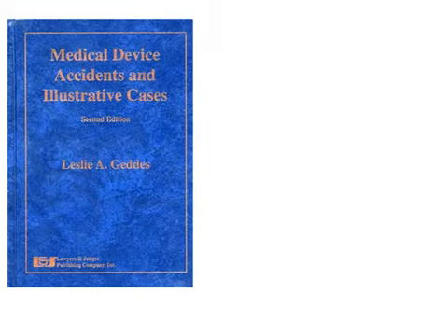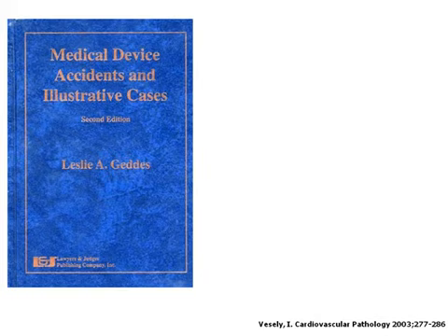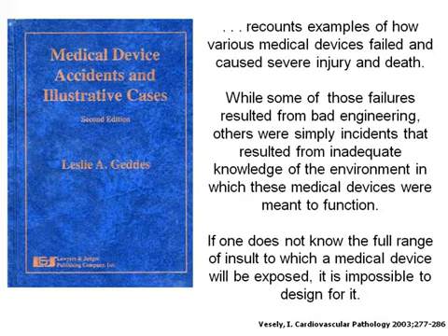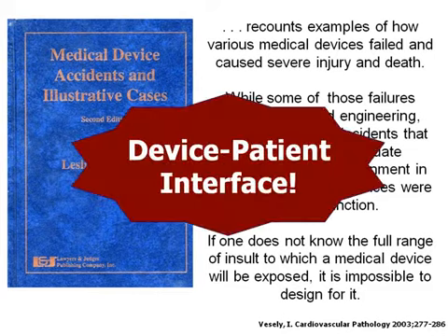This was a book that I came across while preparing for this talk, and it says the following. It recounts examples of how various medical devices failed and caused severe injury and death. While some of those failures resulted from bad engineering, others were simply incidents that resulted from inadequate knowledge of the environment in which these medical devices were meant to function. If one does not know the full range of insult to which a medical device would be exposed, it is impossible to design for it, and this is why we have to understand the device-patient interface.